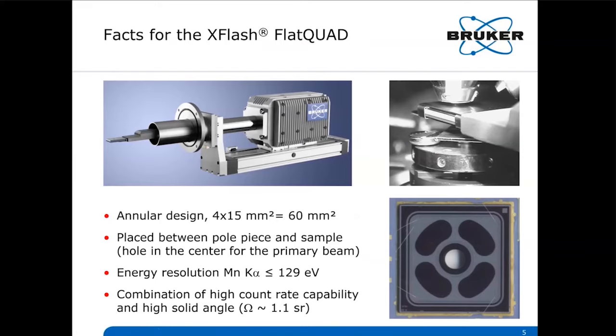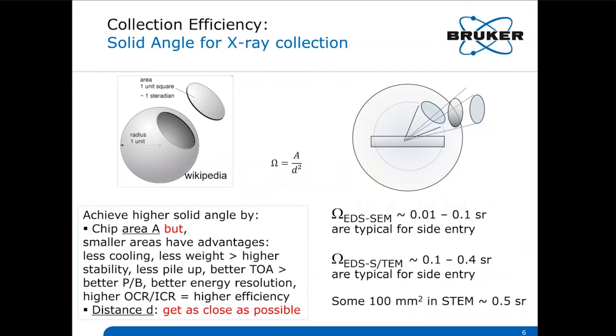The Flat Quad is inserted between the pole piece and sample, as you can see on the top right, with a hole in the center for the primary beam. The four SDD segments each have an area of 15 mm², giving a total of 60 mm² surrounding the hole through which the electron beam passes. Through the combination of the four channels with a maximum of 600,000 counts per second for each channel, the Flat Quad can handle up to 2,400,000 counts per second with a standard energy resolution of 129 eV for Mn Kα.